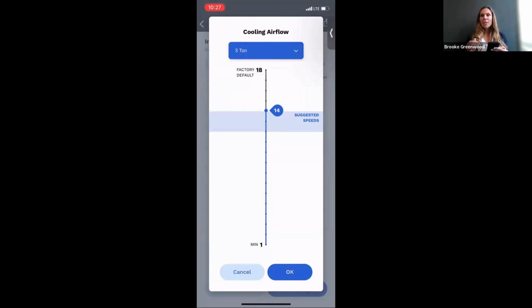This just gives direction of where typical installations would like to be for that size system requirement. Now, if you have higher statics, maybe you need to pick a different airflow, and we highly encourage using the new airflow tables, which we'll also show you this morning from the QR code. It gives you a recommended speed, but you absolutely do not have to leave it within that speed. You can adjust within those suggested speeds, or move outside them. It's just a recommendation. And just to show you it's unique per that outdoor matchup, I selected the 2-ton, and as you can see, my range changed.